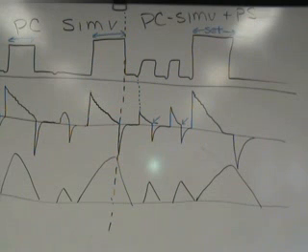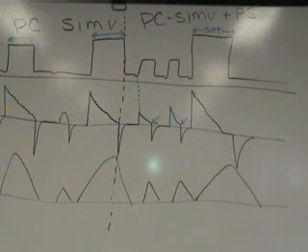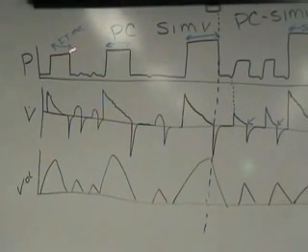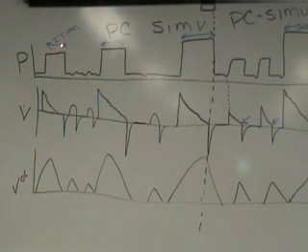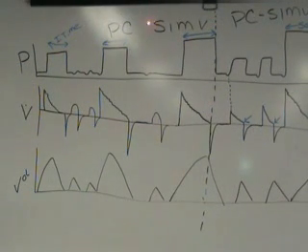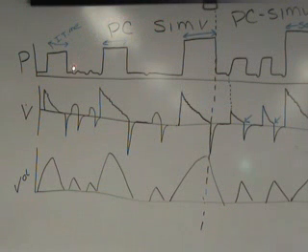The layman's explanation would be, pressure-controlled SIMV: I set a rate, I set a pressure control level, and a set I time. The patient will receive this pressure control level at this set I time for the set rate. If the patient breathes over the set rate, they will receive spontaneous breaths. And the machine will try to synchronize its machine breaths with the spontaneous effort.